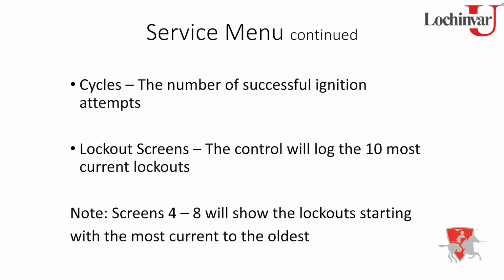Yeah, and one thing I do like to throw out there with the lockout screens, it is handy to have that, especially if you get a call from a homeowner saying, "Hey, I don't have heat, blah blah blah," and you get there and they've reset it, you can actually go in to see what it's locked out on. So if you go in, you see, hey, air pressure switch, and it's been 1.5 years since it's been serviced, you now know the right route to go. So that's where it helps me out, because the hardest unit to troubleshoot is one that's running, and we all know that. So that's something that I always look at when I run into that situation.